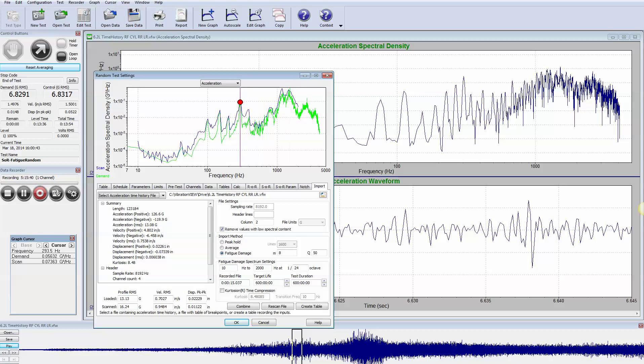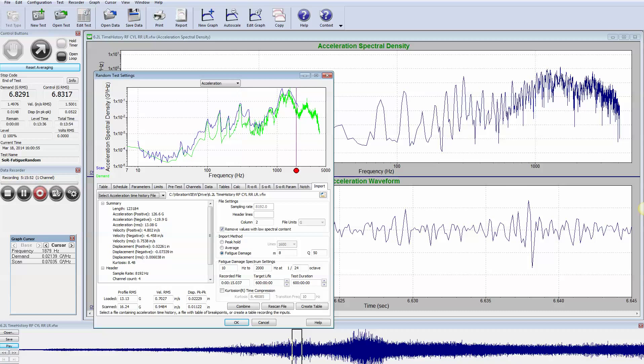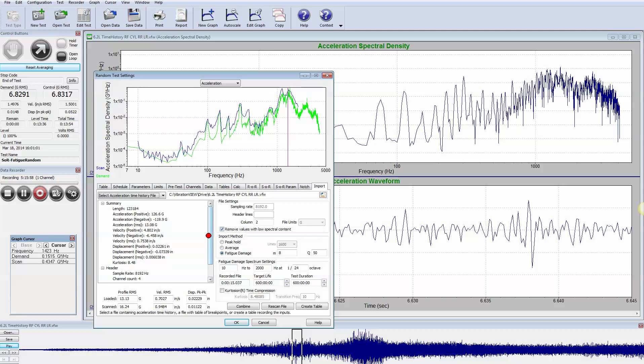So you can see that if you use a damage method you'll get a more accurate random equivalent. The random waveform which is run will give you the same amount of damage as that particular waveform gave you originally, which was of course not random but basically sine on random with sweeping sine tones, i.e. engine run-up.